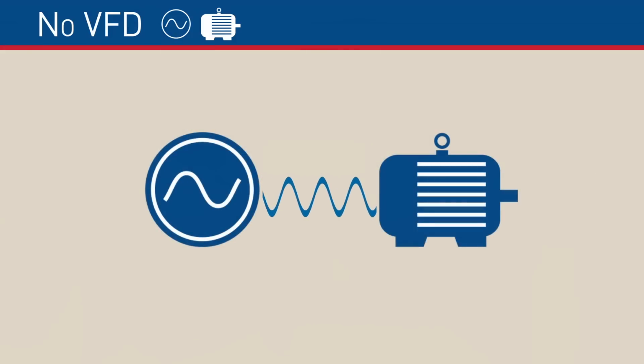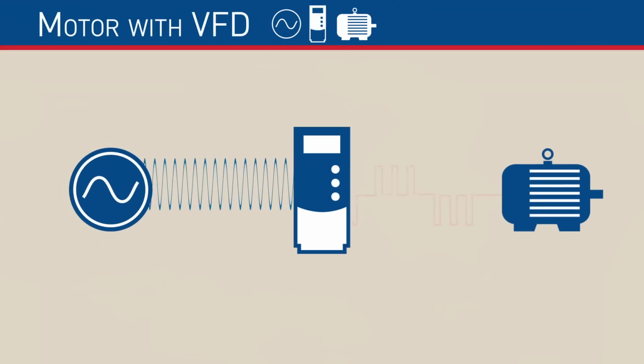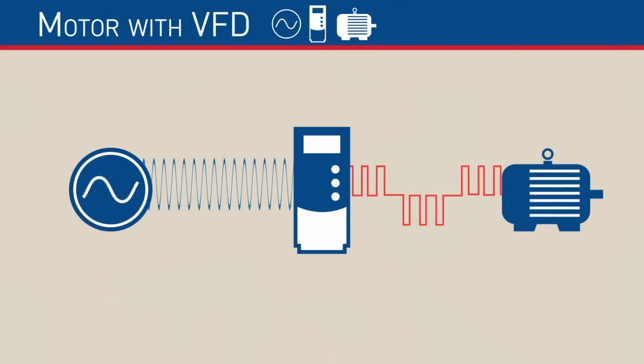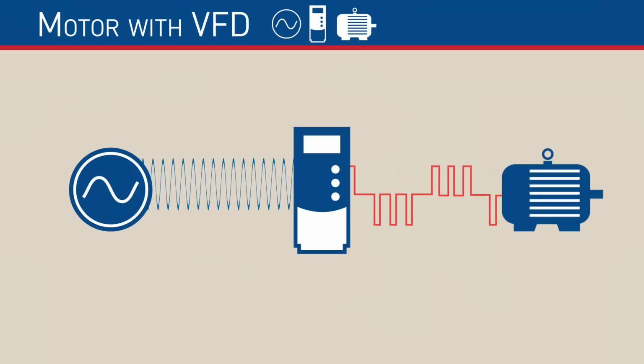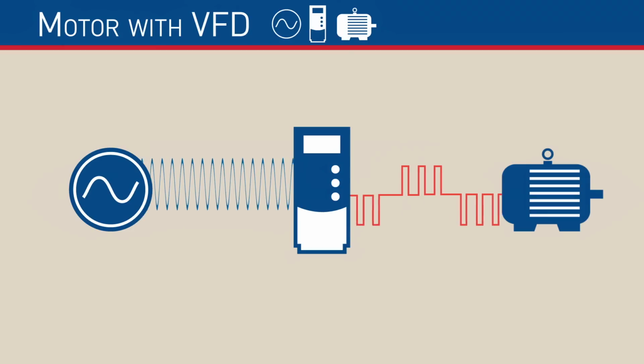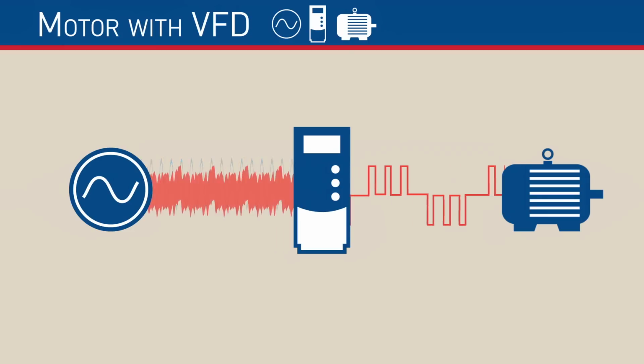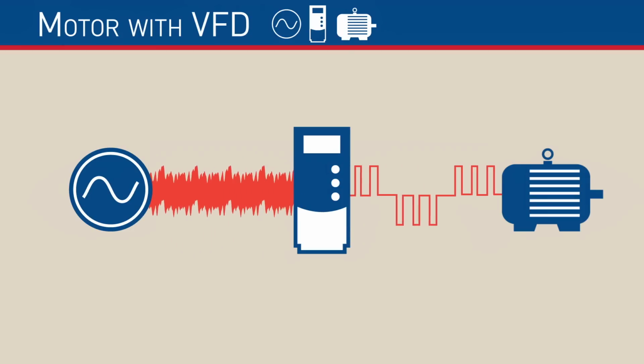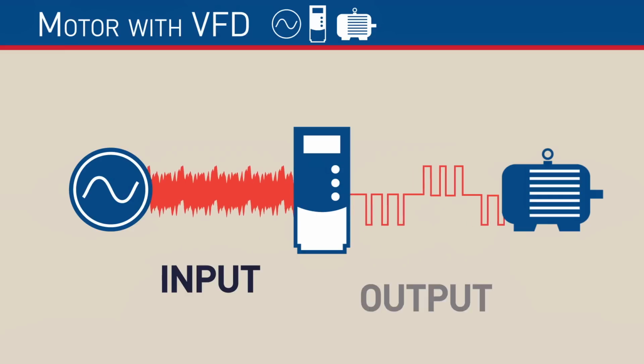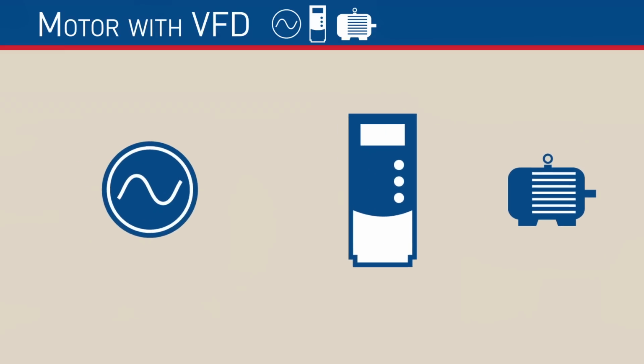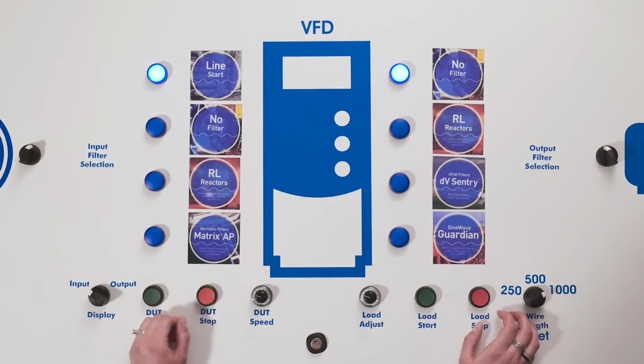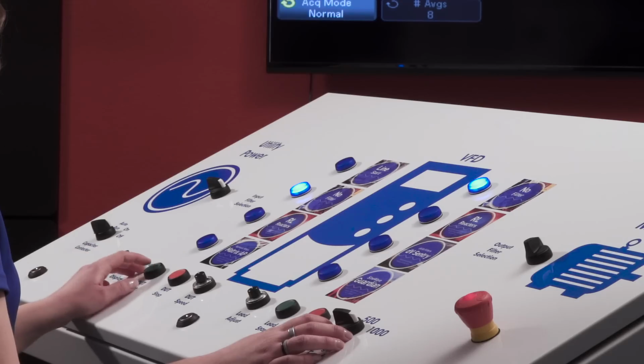When a motor receives power directly from the power source, it's continuously running at its top speed. The motor uses the energy it needs, and the rest is wasted. Adding a variable frequency drive, or VFD, to control motor speed can regulate energy consumption and decrease wear and tear on equipment. Although it adds efficiency, a VFD creates power quality issues on both the input and output sides of the drive. We'll explore the input side first and see what happens when we introduce a VFD to our system.